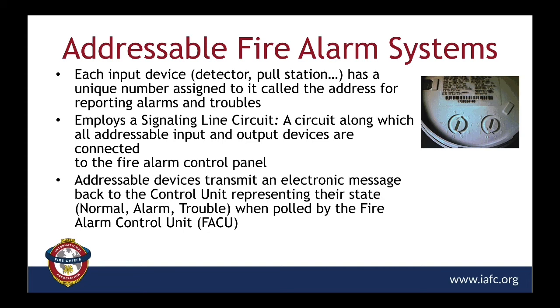So now let's expand and go to what I consider really the most important step the fire alarm industry has taken for the first responder. This actually came about in 1982, when the first addressable fire alarm systems were introduced into the marketplace. The key message here is that each device, detector, or pull station now has a unique number or unique address that is going to be displayed to you when you enter the building.